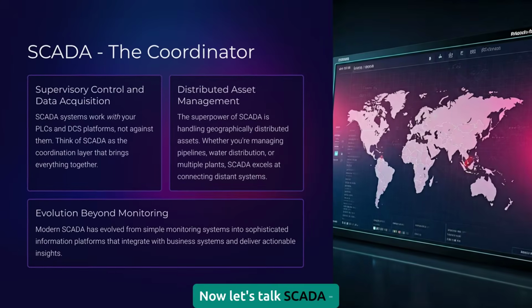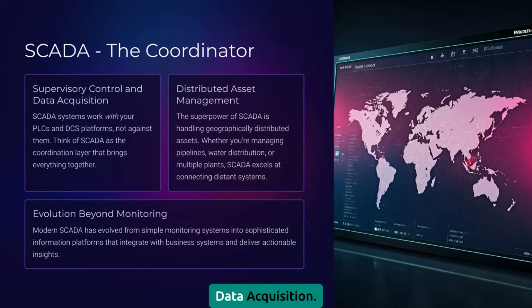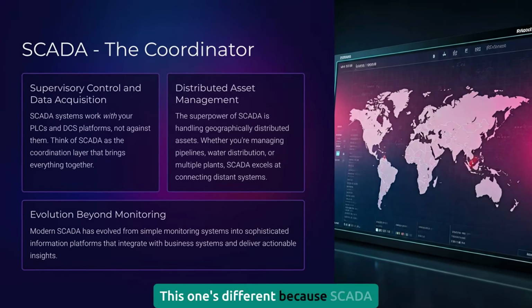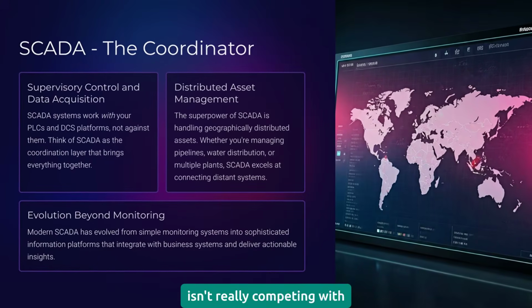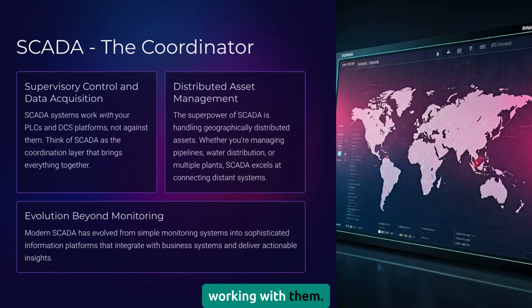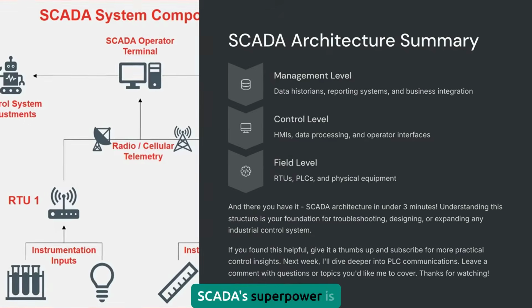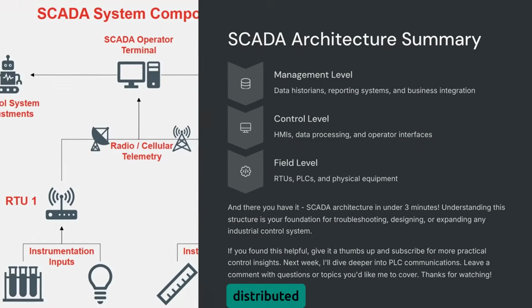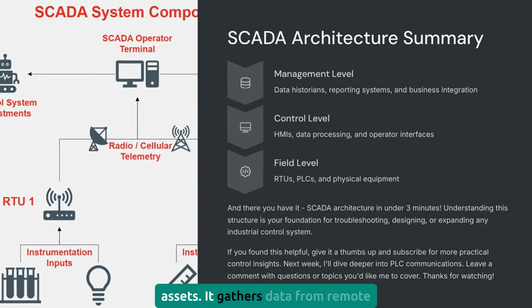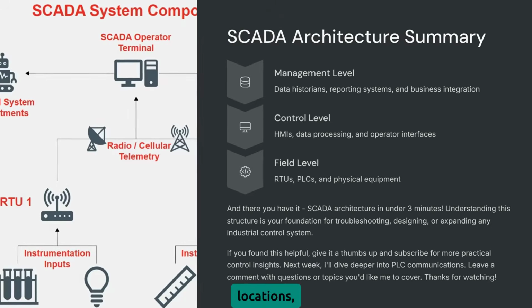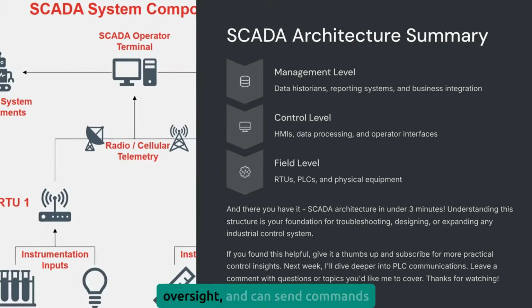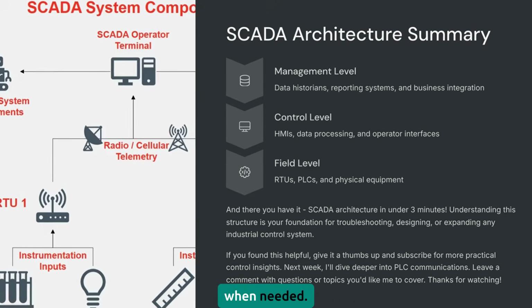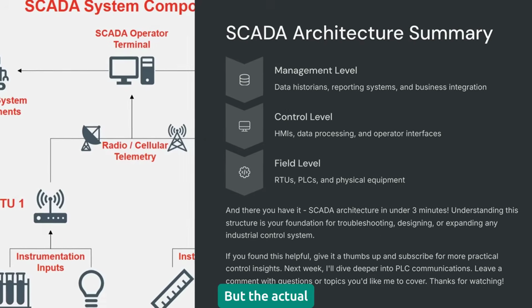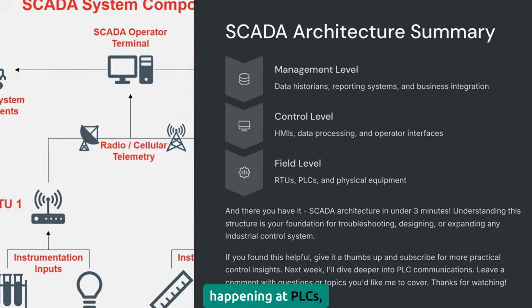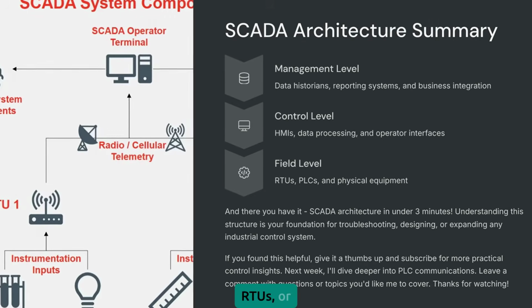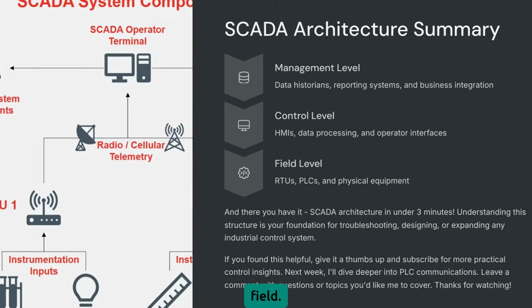Now let's talk SCADA, supervisory control and data acquisition. This one's different because SCADA isn't really competing with PLCs and DCS, it's working with them. SCADA's superpower is handling geographically distributed assets. It gathers data from remote locations, provides operator oversight, and can send commands when needed. But the actual control? That's usually happening at PLCs, RTUs, or even DCS systems in the field.